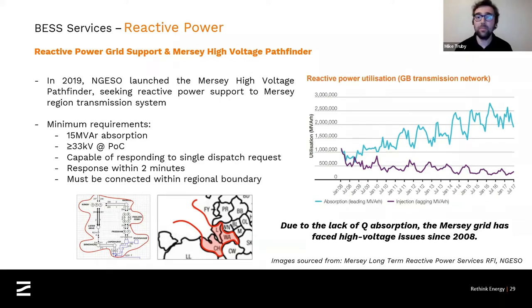I've already mentioned there's a bunch of traditional equipment that can do that, and so a number of parties bid into this service. There was a series of requirements for the service. The main one that I want to call out was the fact that it was regional. Reactive power affects the region around it most prominently, and it affects the voltage of the region around it most prominently. So being local to where the problem is really important, and that's a big part of why the Capenhurst site is where it is.